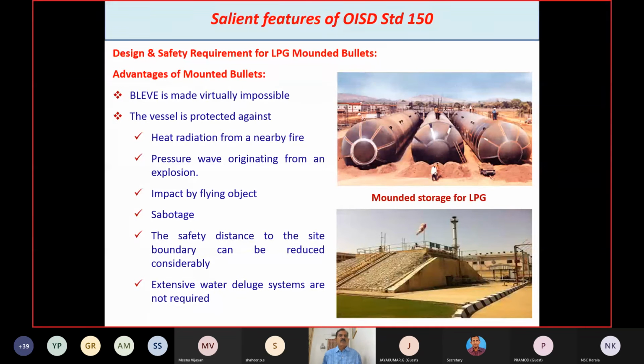The advantage of mounded bullets is that a boiling liquid expanding vapor cloud explosion is made virtually impossible. Actually, this is the worst scenario of LPG storage, the boiling liquid expanding vapor cloud explosion. This is a catastrophic failure of an LPG storage vessel. It commonly occurs in pressurized LPG storage vessels exposed to any external fire and not covered by a stream of water.